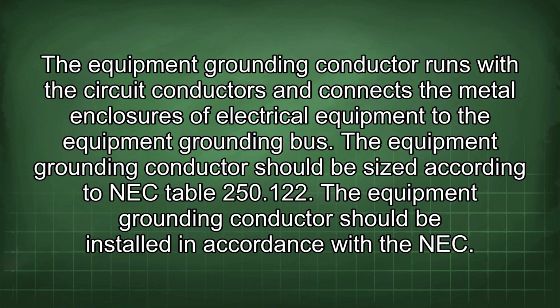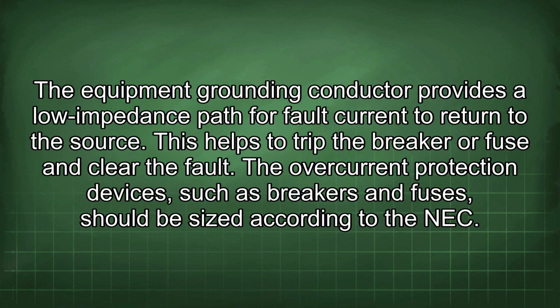The equipment grounding conductor runs with the circuit conductors and connects the metal enclosures of electrical equipment to the equipment grounding bus. The equipment grounding conductor should be sized according to NEC Table 250.122. The equipment grounding conductor should be installed in accordance with the NEC. The equipment grounding conductor provides a low impedance path for fault current to return to the source. This helps to trip the breaker or fuse and clear the fault.